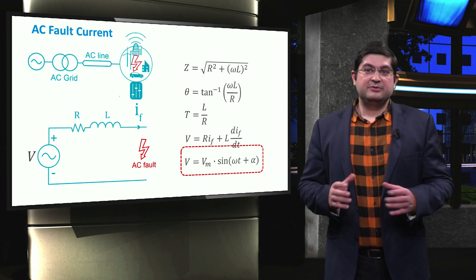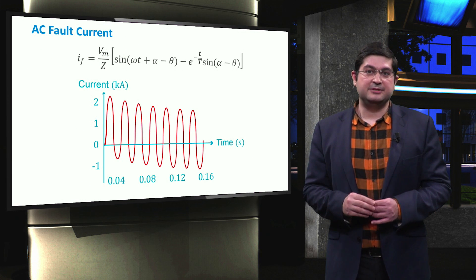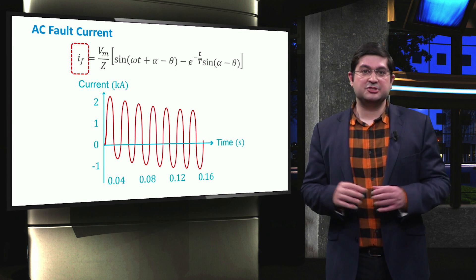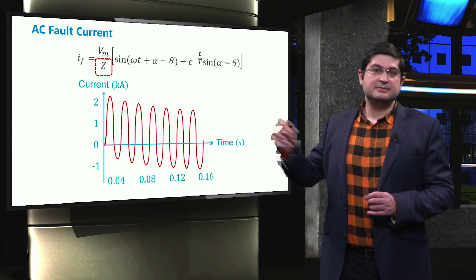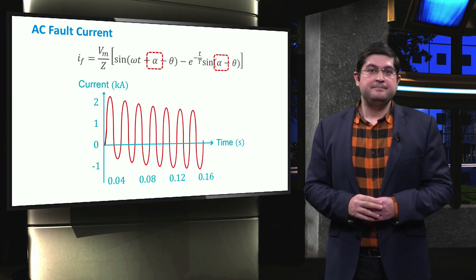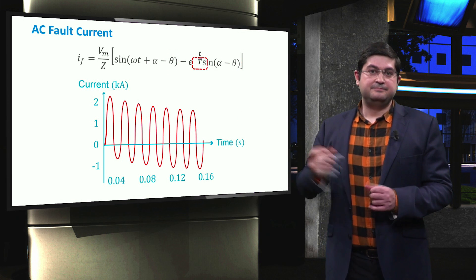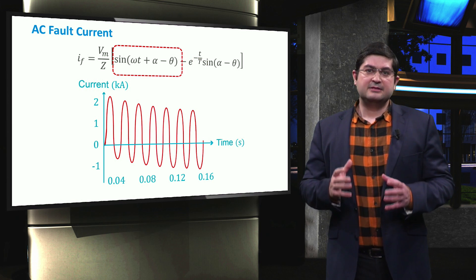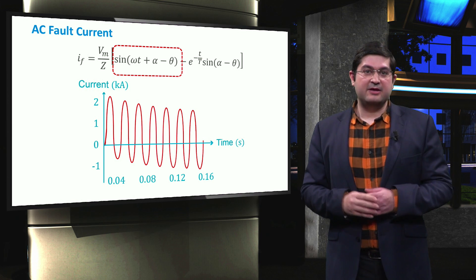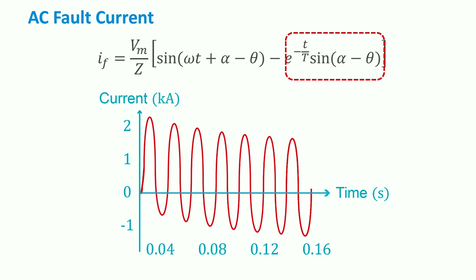Note that here we do not formulate the fault impedance. If we solve the previous differential equation, the fault current IF is obtained as a function of the voltage amplitude Vm, the amplitude of the impedance Z, the angular speed omega, the initial phase alpha, the impedance phase angle theta, and the time constant T. This equation represents two different components: the first is the steady-state AC sine wave with the angular speed omega, and the second is a DC exponential decay with the time constant T.